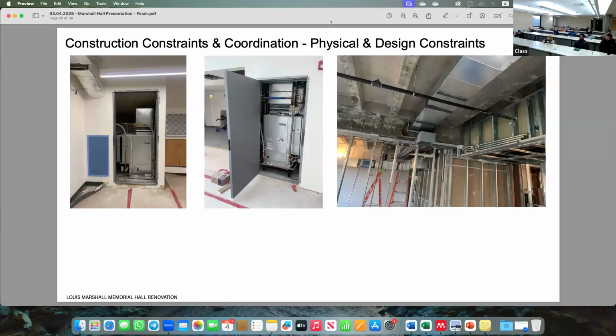But what we can change is, if I need to get through this structural beam, which is what that is right there - I'll get into that in a minute - it's easier for me to thin this ductwork up, but there's a ratio I have to follow. Quinn designed a certain amount of CFM to get from point A to point B, so I can't just neck it down to make it fit, because then I'm not going to deliver enough CFM.